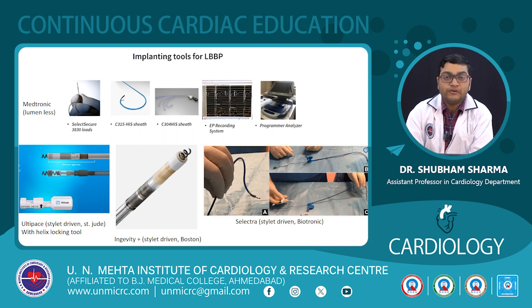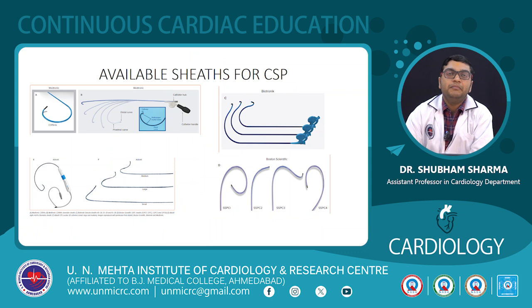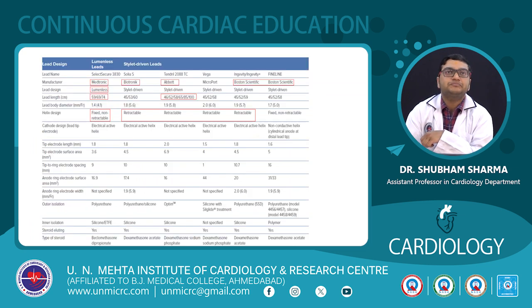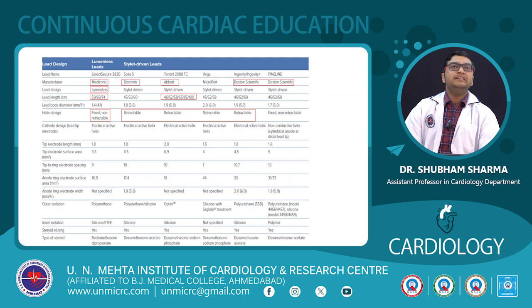Coming to the implantation tools for left bundle branch pacing. Initially, it was only Medtronic which used to provide a lumenless lead, that is the SelectSecure 3830 lead, compatible with the C315 sheath for left bundle pacing. But now, as the competition has grown, different players have come up. We have a stylet-driven lead provided by St. Jude, Boston and Biotronik. We do have pre-shaped or pre-curved sheaths which have a primary and secondary curve, which makes it much easier to direct the lead towards the septum. So now we have stylet-driven leads, and Medtronic only is supplying the lumenless leads.